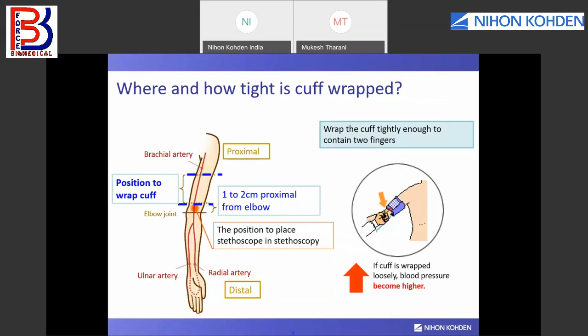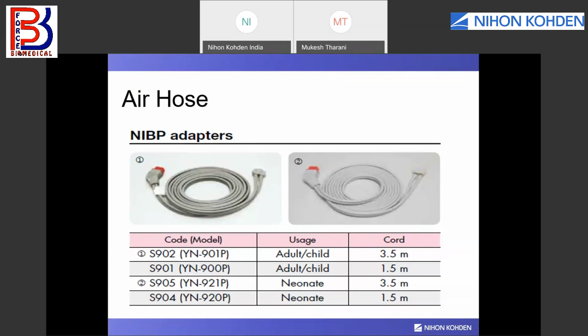The cuff is connected with the patient monitor through a tube called the air hose. The air hose is the tube which carries the air pressure from the patient monitor to the bladder inside the cuff. It also comes in a variety of sizes depending on the requirement, the location, and the position from the patient monitor to the patient bed. So you can choose the air hose length.